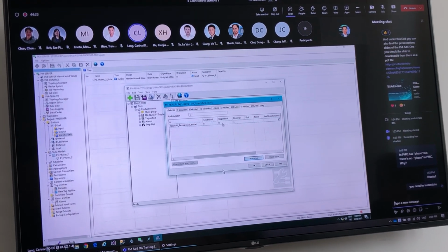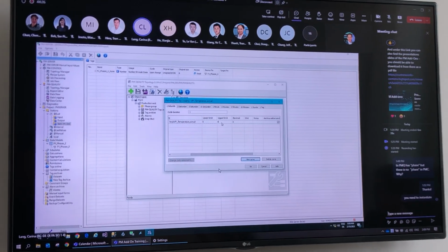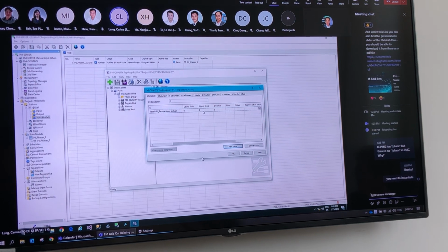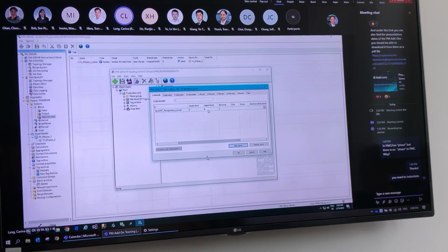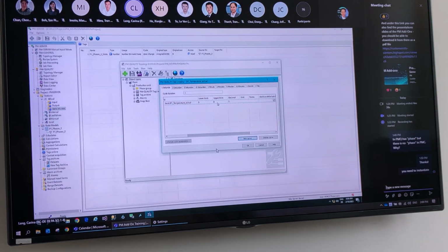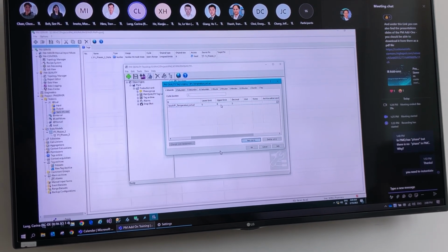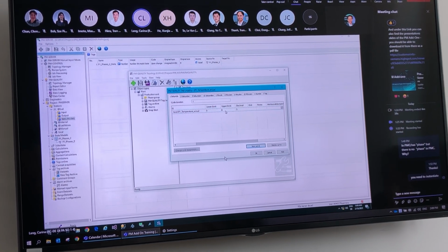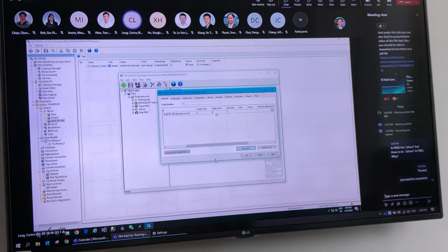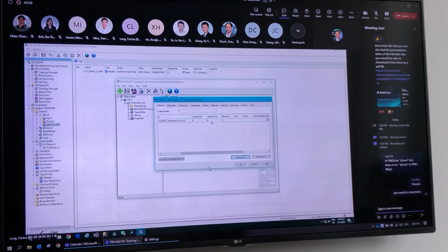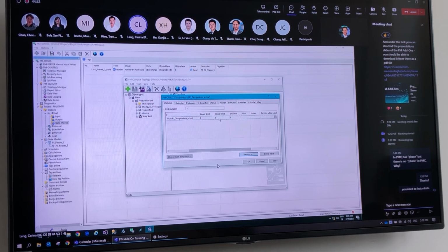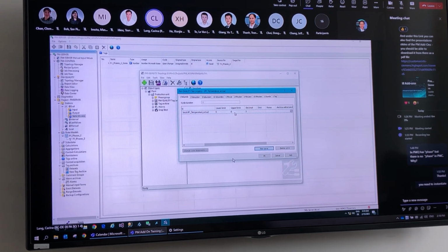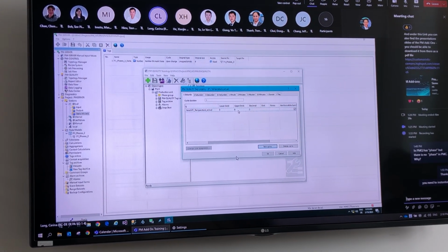PIM quality does not say, okay, you're higher than the upper limit, so I do not record this value. No. PIM quality is just recording all data coming from this tag, so all values, and the limitations are just for the diagram so that you can have the value axis from the lower limit to the upper limit, but this has nothing to do with recording the curve values.